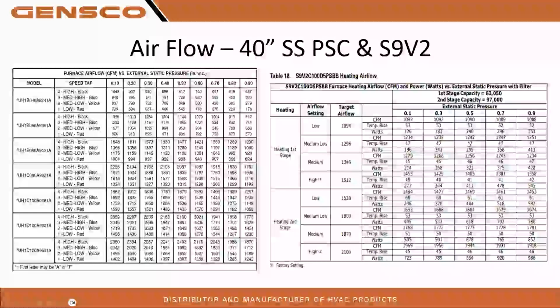So then we're actually giving you the temperature rise that you should be at, 47. And then we're actually giving you the watts of the blower motor. Okay. So we're giving you all you can. You simply need to pull the static number to be able to verify that. Okay. So all these are marked factory settings. So from the factory, first stage is going to be high, second stage will be high, and of course you can adjust it down depending on what you need here.